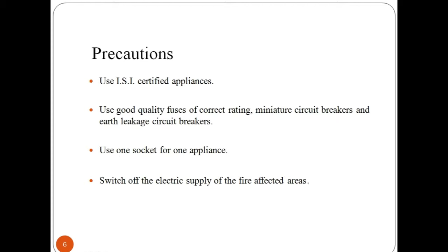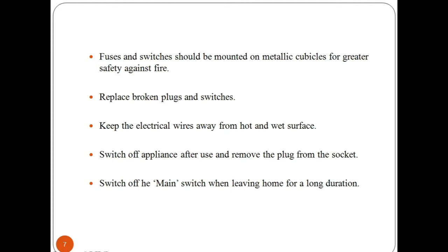Another precaution to be taken is that fuses and switches should be mounted on metallic cubicles for greater safety against fire. If you notice any breakage on plugs and switches, then immediately replace them. Electrical wires should be kept away from hot and wet surfaces, as they can instantly react and remove insulation and make conductors short-circuited when they come in touch with each other. Switch off appliances after use and remove the plug from the socket.